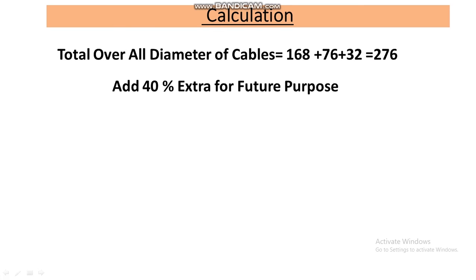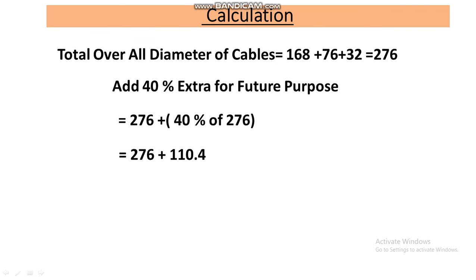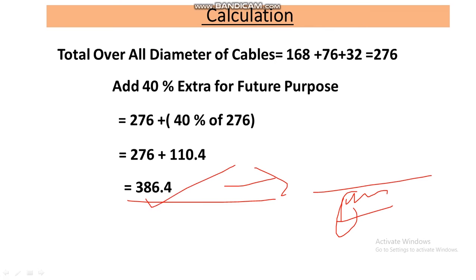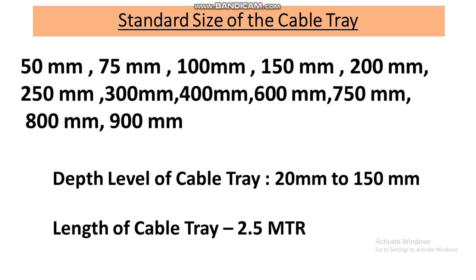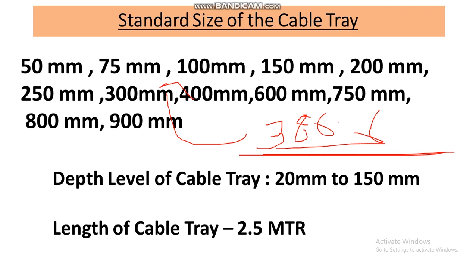Now we add 40% extra for future use — this is the safety factor. So 276mm + 40% of 276mm = 276 + 110.4 = 386.4mm. This is the required width of the cable tray. Looking at the standard sizing table, we always go for the next higher value, so 400mm is the closest standard size above 386.4mm.